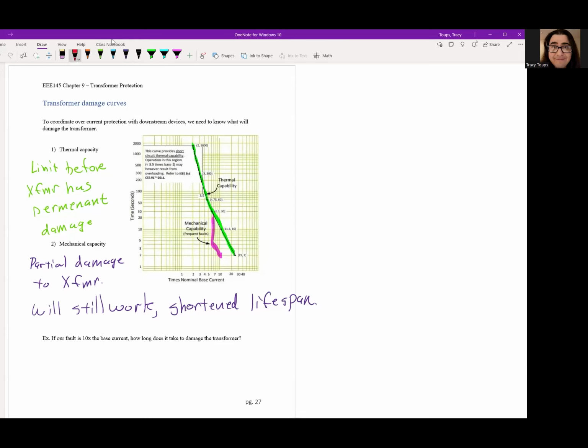So if we have a 10 times fault on the base current, how long will it take for the transformer damage curve to start? Well, remember how faults work. So here, we're going to go at 10x, which is right here, 10 times your nominal current. You go up here, and we're going to hit this point right here. This is where we hit the mechanical curve. What's that cross-reference number? It's about right here. So we know that after 2 seconds, we will partially damage the transformer. Okay.